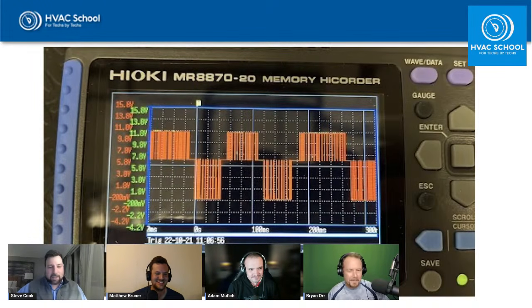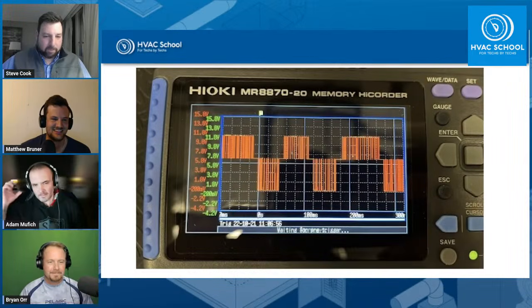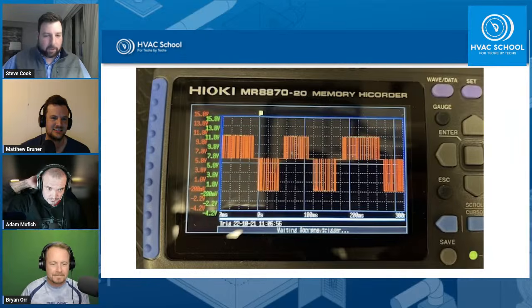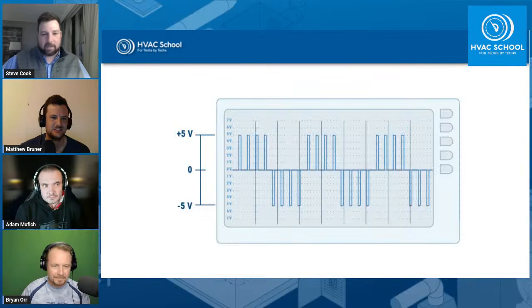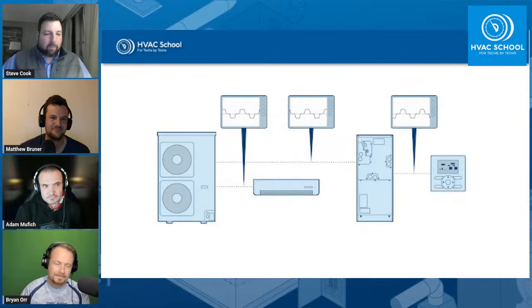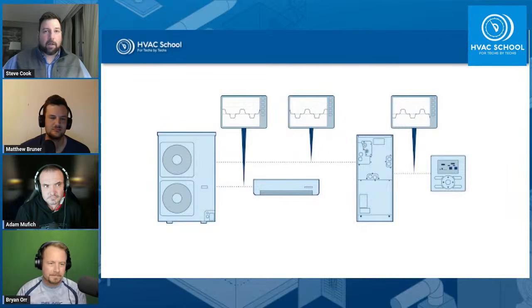But you'll never see this on a system. If you take your meter, you'll never pick it up. You will pick up the voltage signal -- let's just say Mitsubishi. If you're reading from M1, M2 on a communicating VRF system, City Multi, you'll pick up 29 volts. But you're not going to see what's going on, because in a VRF system there could be thousands of communications happening at any given moment, unless everything's off, which is highly unlikely.